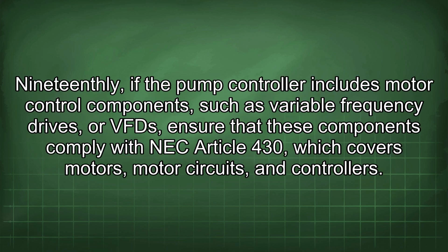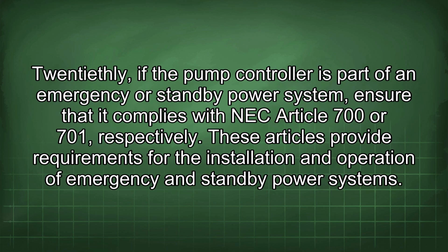19thly, if the pump controller includes motor control components, such as variable frequency drives, or VFDs, ensure that these components comply with NEC Article 430, which covers motors, motor circuits, and controllers. 20thly, if the pump controller is part of an emergency or standby power system, ensure that it complies with NEC Article 700 or 701, respectively. These articles provide requirements for the installation and operation of emergency and standby power systems.